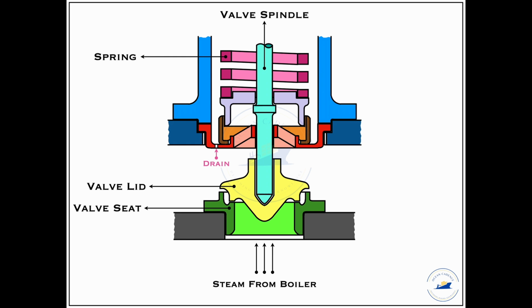That is, these passages should not be choked, because as you can see, the steam, once it escapes and goes out to the upper piston side through the underside passage, then once the steam gives the high lift for the high lift safety valve through the steam piston, then after condensing, this steam has to find a passage to drain back and go through the drain line and finally collect it to the drain side.